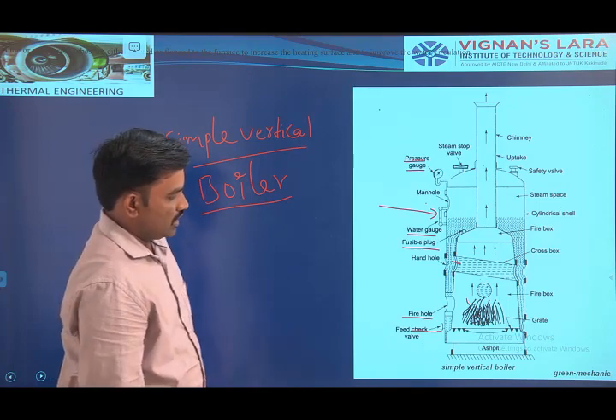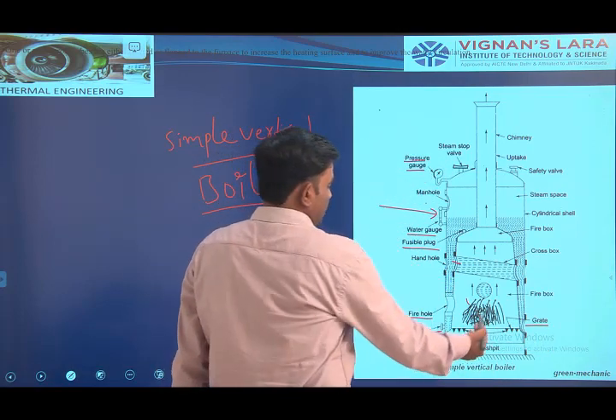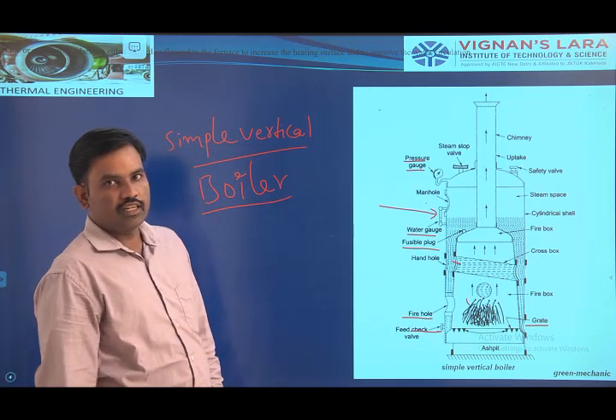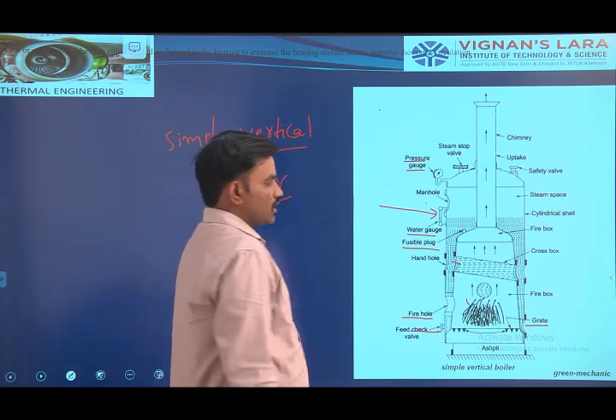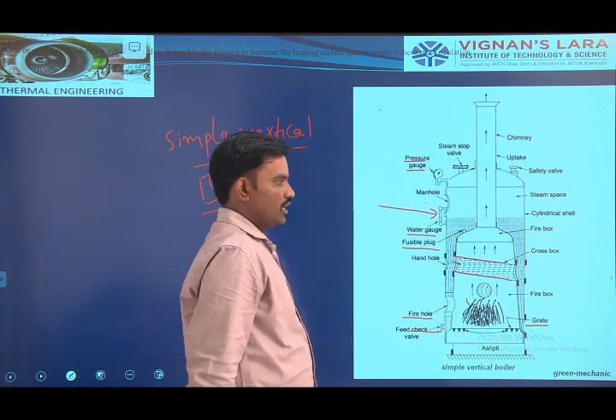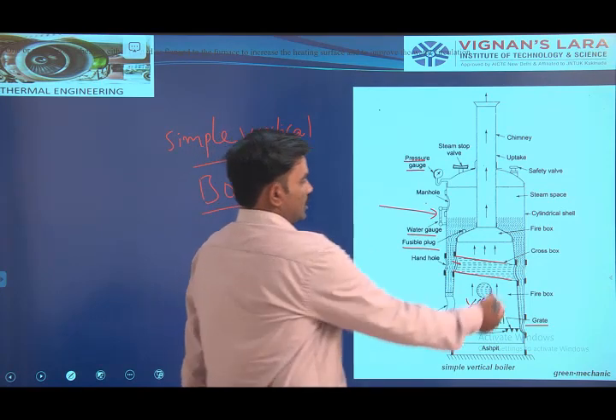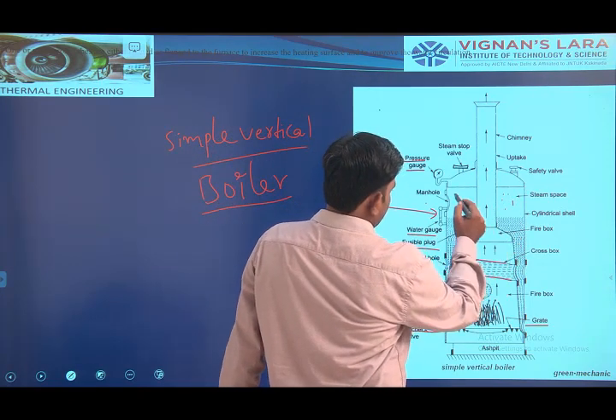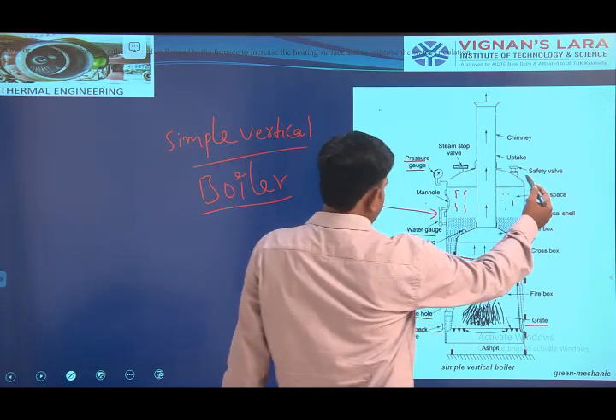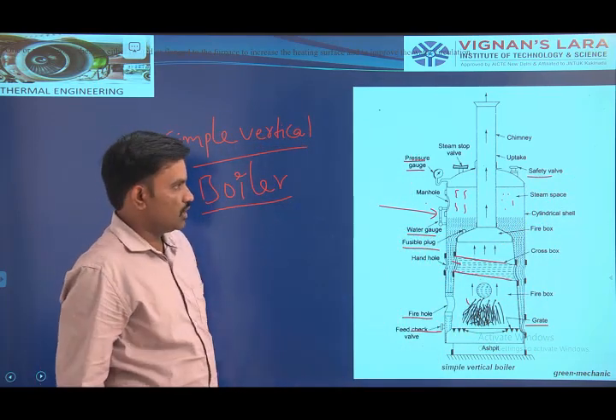It is a fire tube boiler. In case of the grate, we are introducing coal onto the grate and burning it inside the boiler combustion chamber. In case of the cross box, we are arranging a number of horizontal tubes for increasing the heat transfer area. The cylindrical shell is the boiler shell. In case of the steam space, we are generating and collecting the steam. With the help of the safety valve, we are releasing excess pressure generated by the steam inside the boiler section.